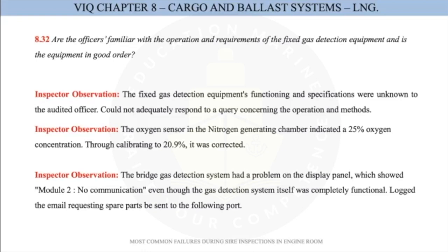Again, it should be this maintenance remark. Because normally, it should be in your maintenance plan, the PMS system. Or maybe you didn't have the span gas for calibration. You received it, but it was forgotten, not marked in handover and in your remarks. And after that, it ended up as an observation.